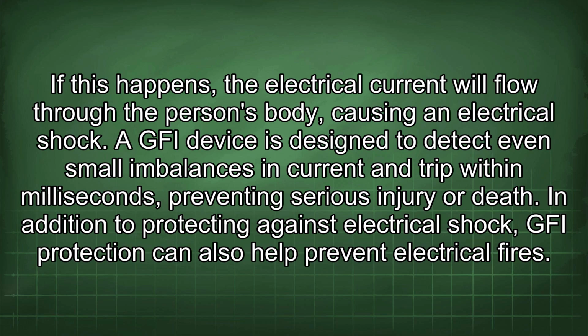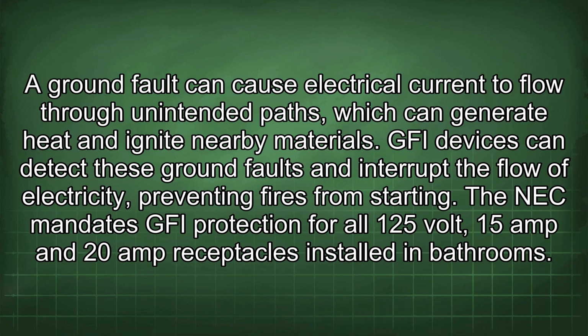In addition to protecting against electrical shock, GFI protection can also help prevent electrical fires. A ground fault can cause electrical current to flow through unintended paths, which can generate heat and ignite nearby materials. GFI devices can detect these ground faults and interrupt the flow of electricity, preventing fires from starting.